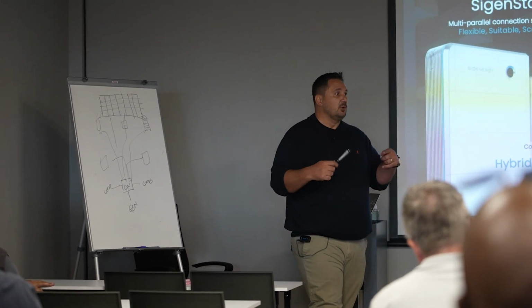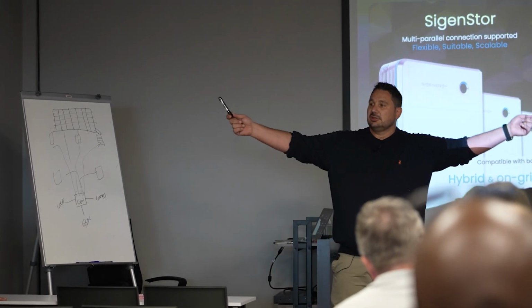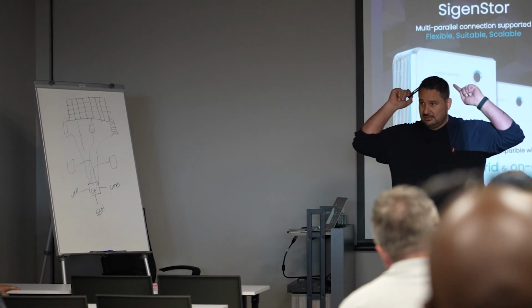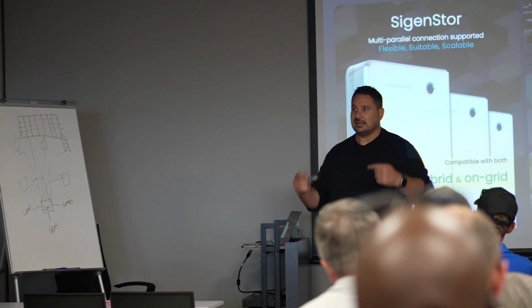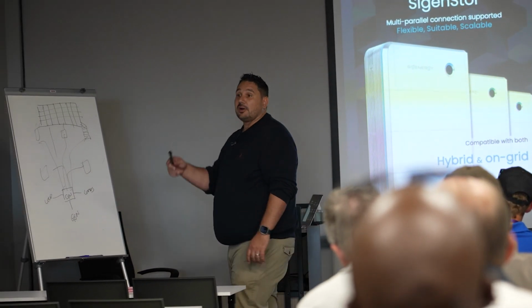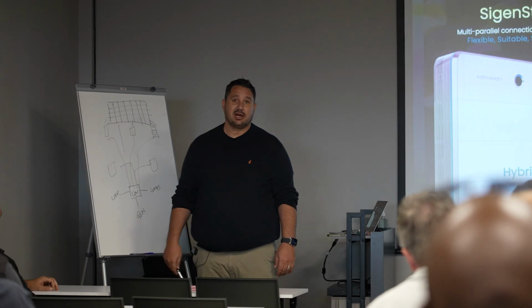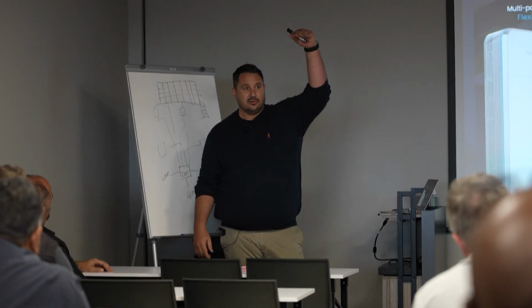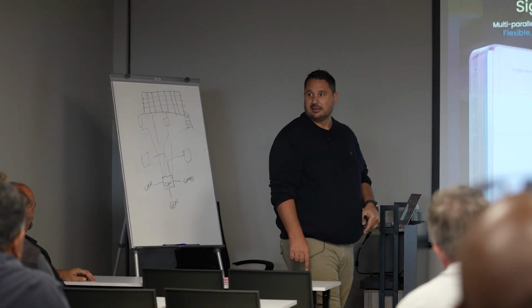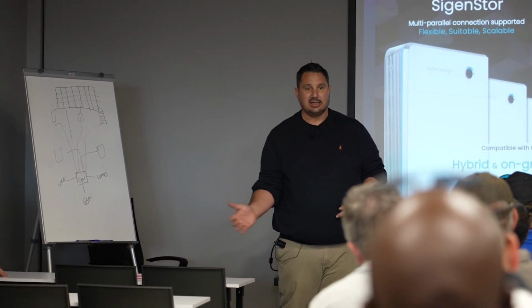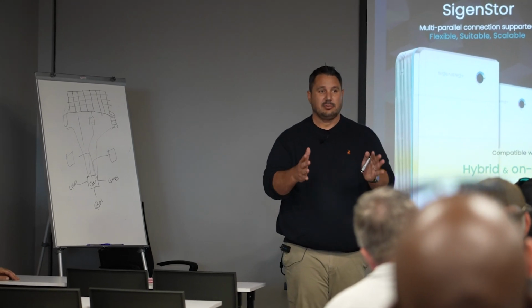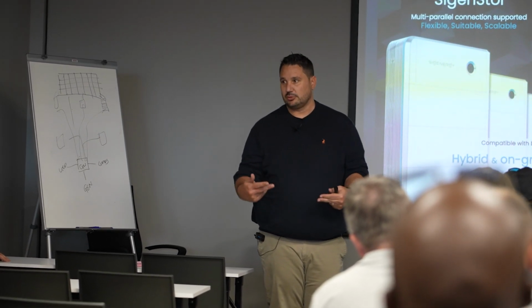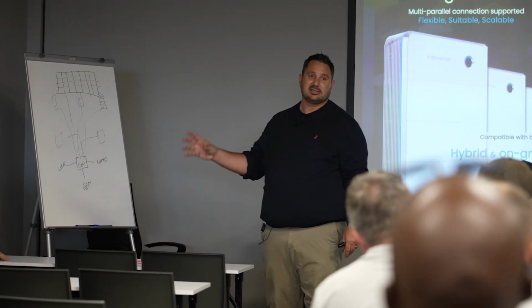Take this building. We could stick SigenStors around the outside and just feed all the AC cables to the inside. You've got a building that's 5 stories high, PV on the roof. Stick the inverters under the PV modules. Short DC runs. Bring all the AC cables down in the services shaft. In the basement where your connection normally is, put your gateway, come in with your AC cables all into your gateway. So your gateway is a fully AC connected system.